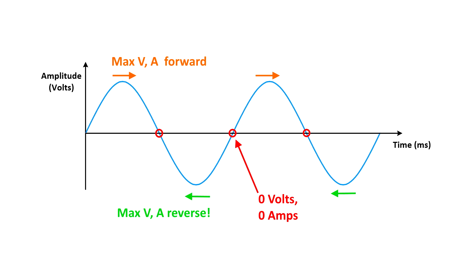And now the thing is with AC, it's kind of easy because as we can see on our little graph here, that's the sine wave representing alternating current. And as you'll notice where the little red circles are, at those points, the alternating current reverses directions, which means at those points, you have zero volts and zero amps. Now why that matters is because if you have contacts in a high voltage AC circuit breaker and you start to pull it out and an arc forms, dozens of times a second, that alternating current is hitting zero volts and zero amps, which means the arc essentially extinguishes itself.